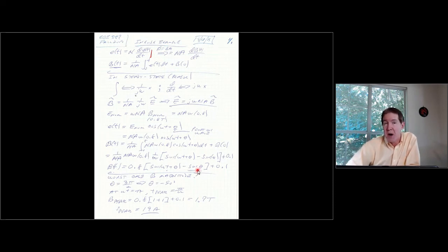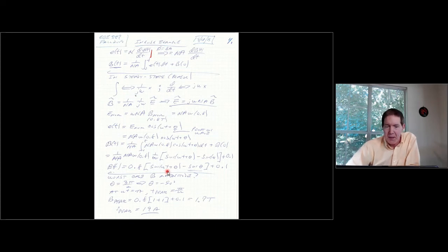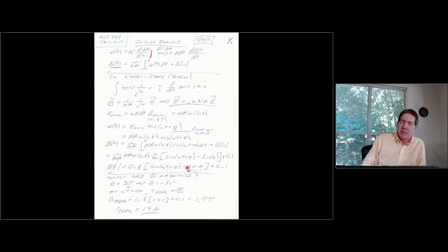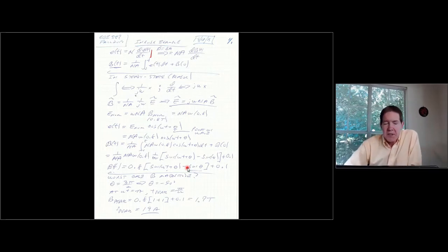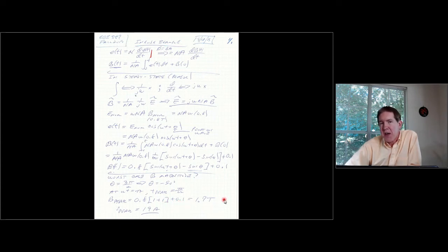The maximum value of the bracket term occurs when sin θ = −1, so I set θ = 3π/2, which is −90 degrees. When ωt = π — that is, after one half cycle at t = π/ω — this term in brackets reaches its peak value of 2. So the peak value of B is 0.8 × (1 + 1) = 1.6, and adding the residual 0.1 gives a peak flux density of 1.7 Teslas associated with this energization.